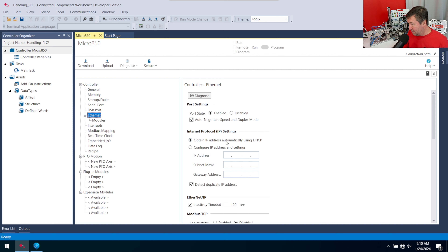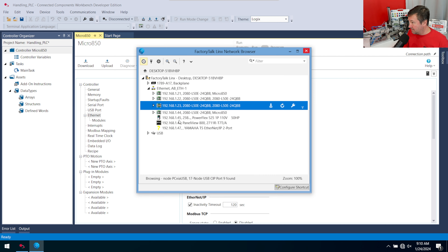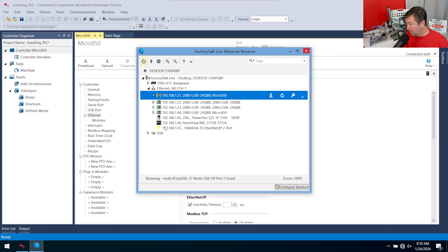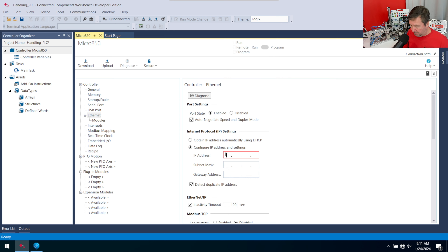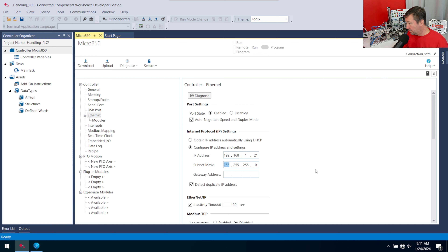Select and add to project. It's very important that we set the IP address of our PLC and know exactly which PLC's IP address we're using. A lot of people get confused on this — you really need a spreadsheet or some way to track your IP addresses in the field. This one will be 192.168.1.21, with a default subnet of 255.255.255.0.